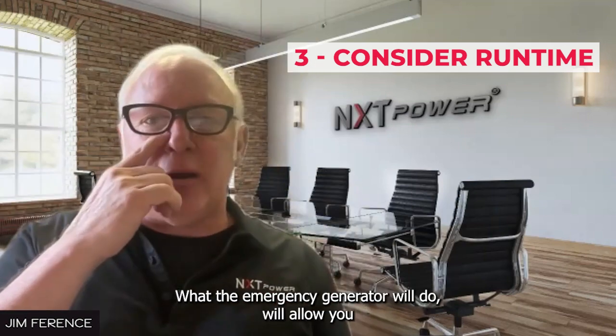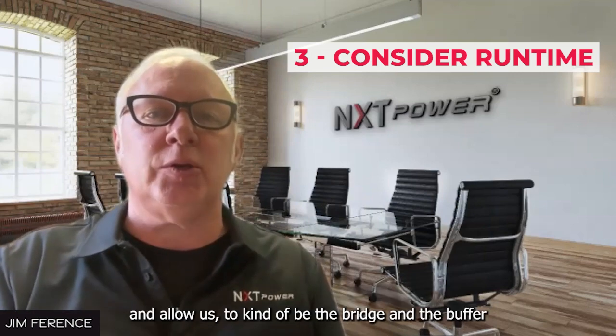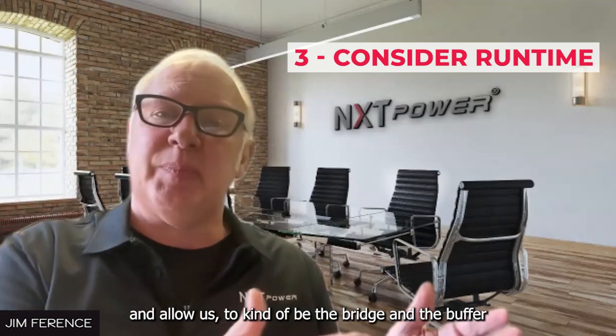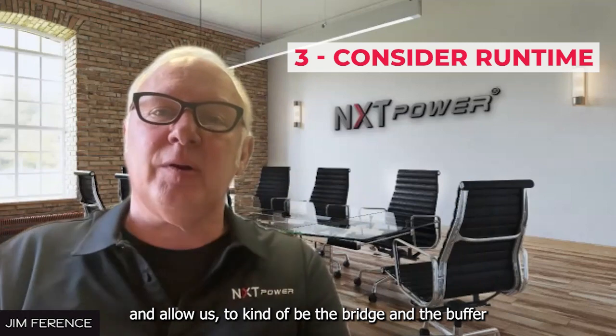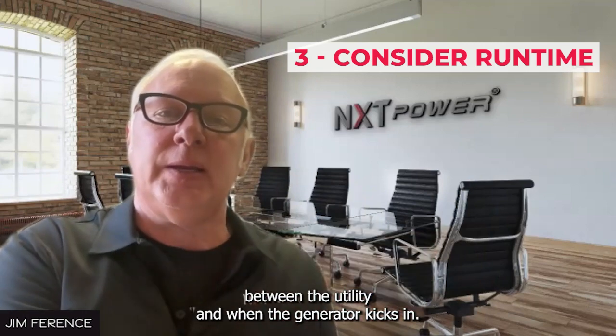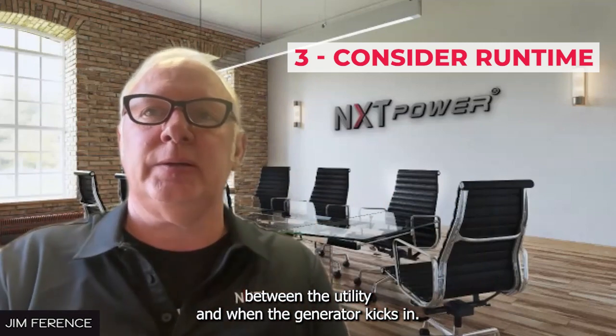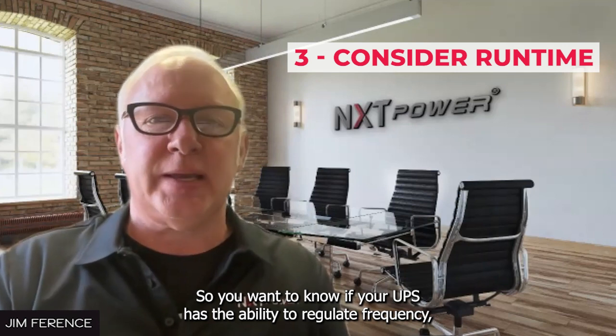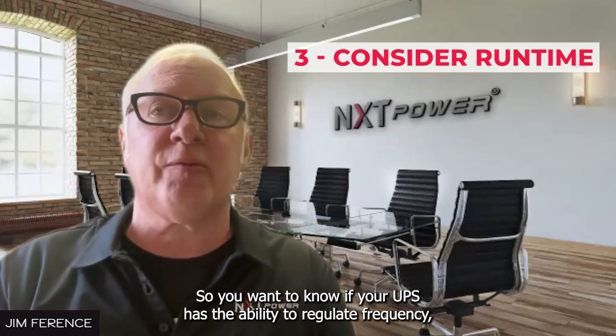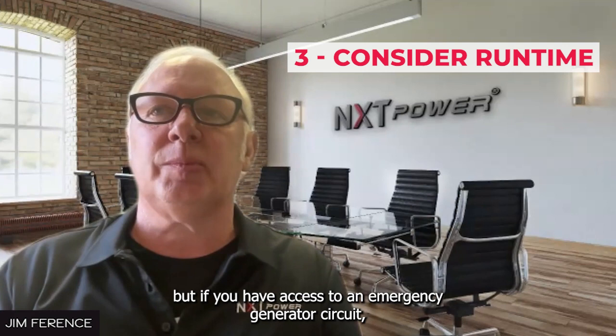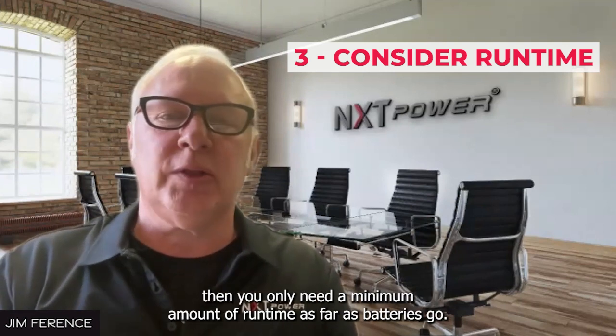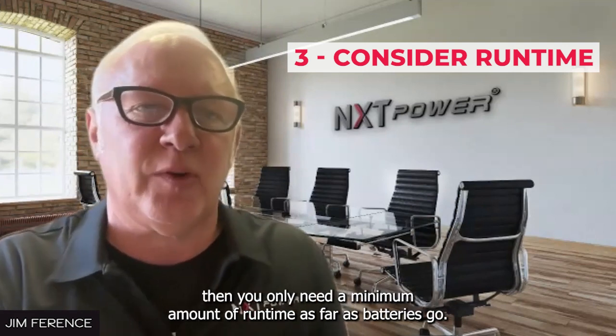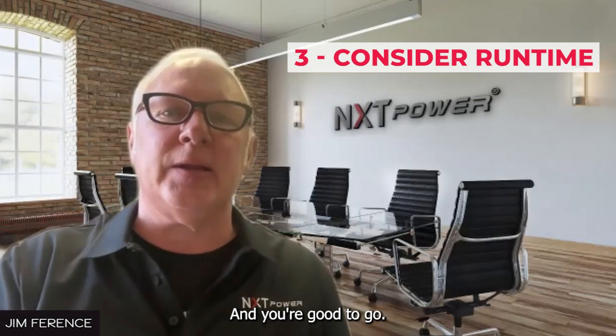What the emergency generator will do is allow us to be the bridge and buffer between the utility and when the generator kicks in. So you want to know if your UPS has the ability to regulate frequency. But if you have access to an emergency generator circuit, then you only need a minimum amount of runtime as far as batteries go, and you're good to go.